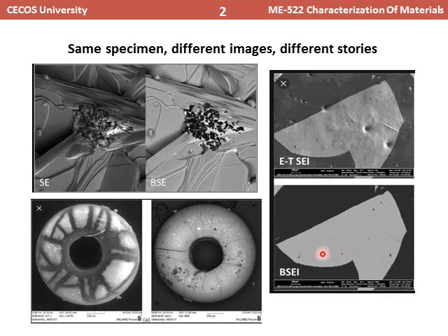In backscattered electron, because the electrons are penetrating much deeper into the skin of the specimen, you will see a flat surface, not these contours. These contours on the surface can only be viewed in the secondary electron image formation, not in the backscattered electron. In backscattered electron, you have a very clear contrast between the images of the very same specimen, and there are some artifacts.